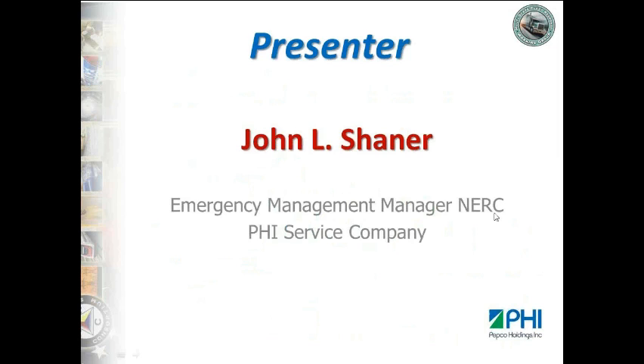Thank you. How are governments notified of grid issues? As I talked about before, and I'm going to focus on my experience, throughout my career I had some responsibility to NERC standard EOP-004, which I know there are some changes coming to, but that is reporting to FERC, NERC, your regional reliability coordinating groups such as RFC, the one I'm familiar with. You're reporting to your ISO, RTO, to your state agencies, and to the federal government through reports such as the OE-417, which is a DOE report that goes from curtailments to load shedding to weather events.